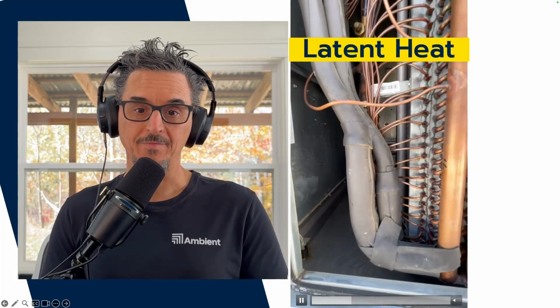Okay, so latent heat. This is a makeup air unit in the summer in the Carolinas. So you can see a lot of latent heat being pulled out of the air from this system. This image is actually from an AHR show last year in Orlando. You can see the sources of sensible heat here would be the lights, the displays, any demos that are plugged in. There's a bunch of TVs in here. And then the latent heat source primarily would be from the people or any infiltration that would be coming into the building.